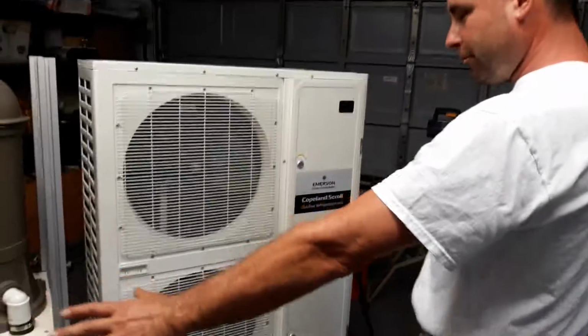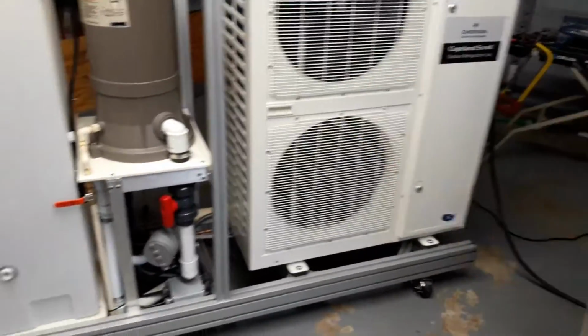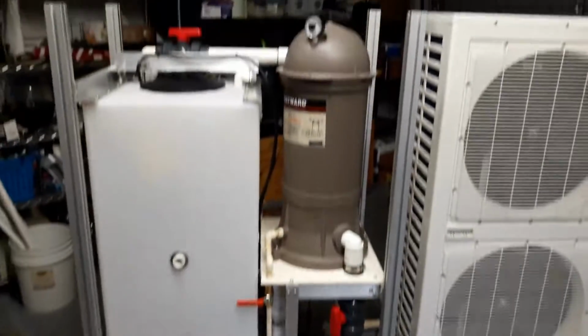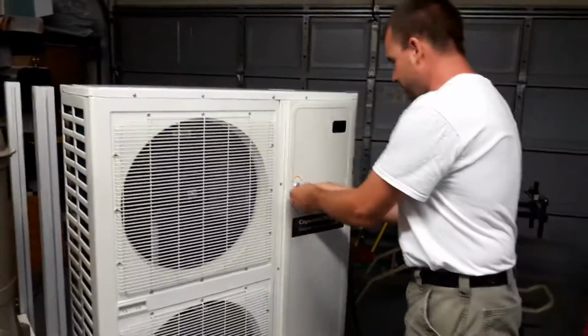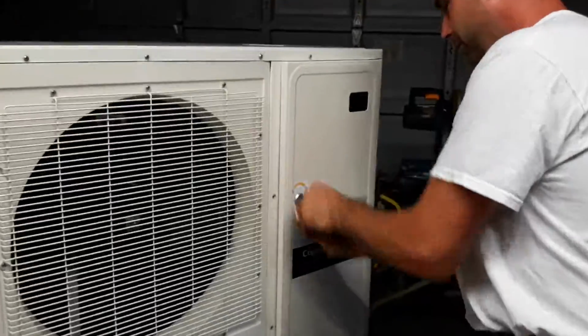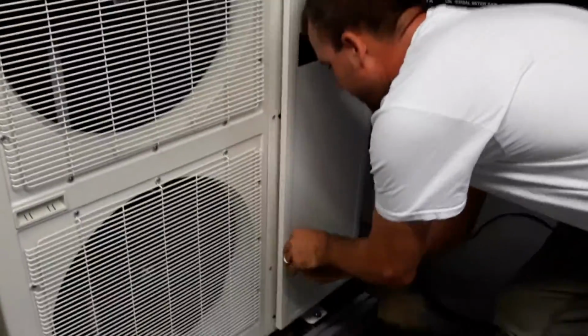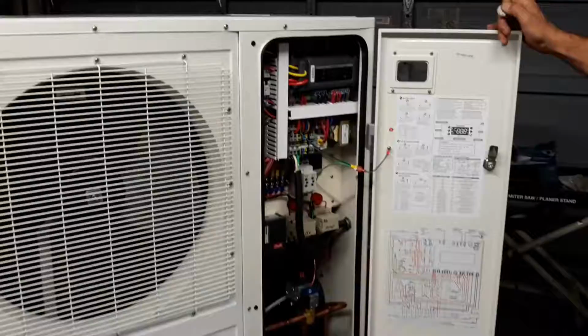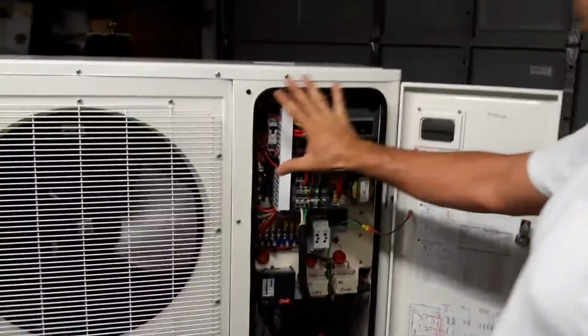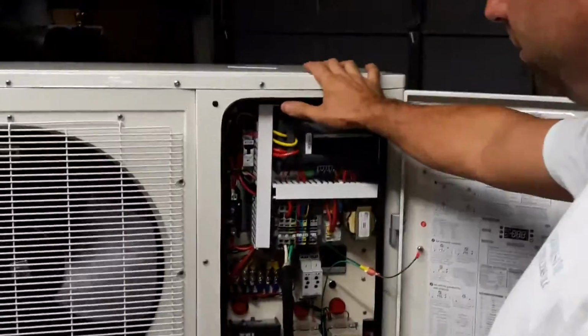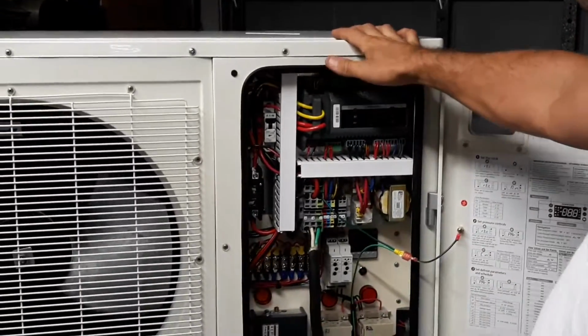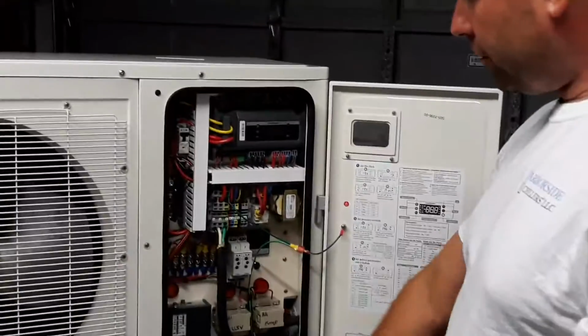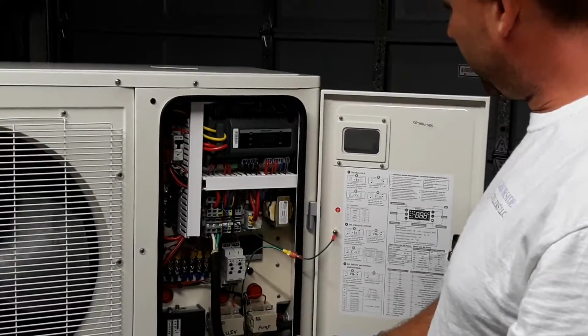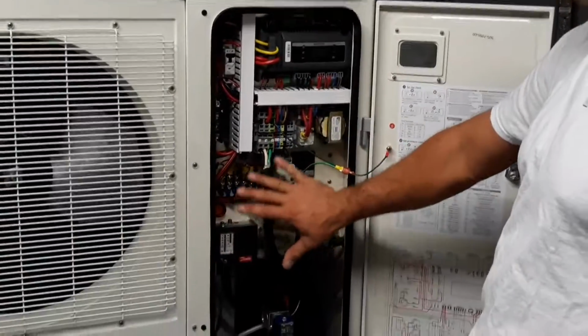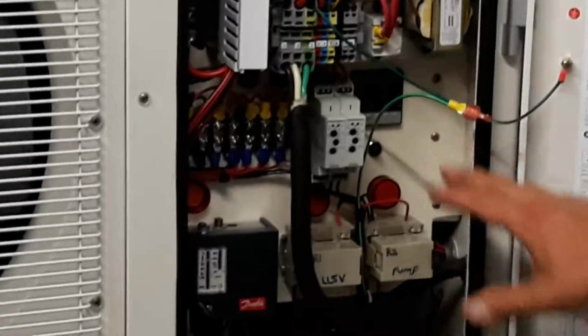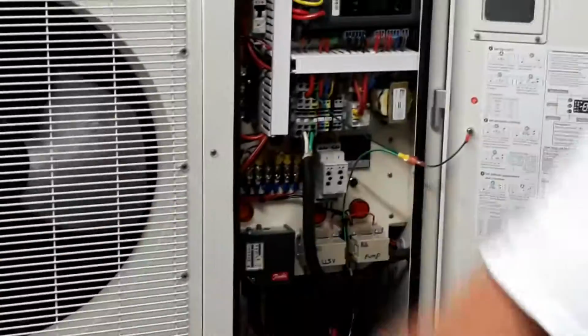Everything is mounted on an aluminum frame, 3/16 stainless. All you need is a quarter to enter your control panel of the machine. And inside this is the factory original components of the condenser, made by Copeland, which controls the compressor and fans and all of that. This is all additional down here, added to control the chiller system.